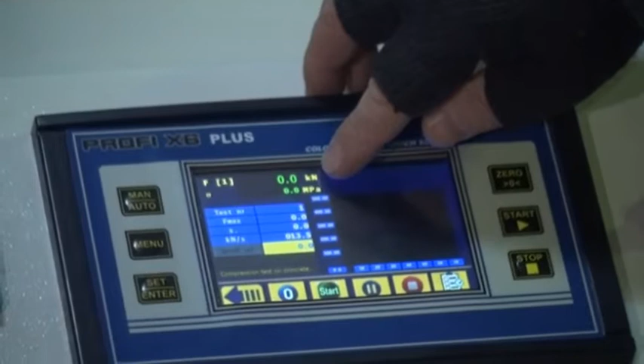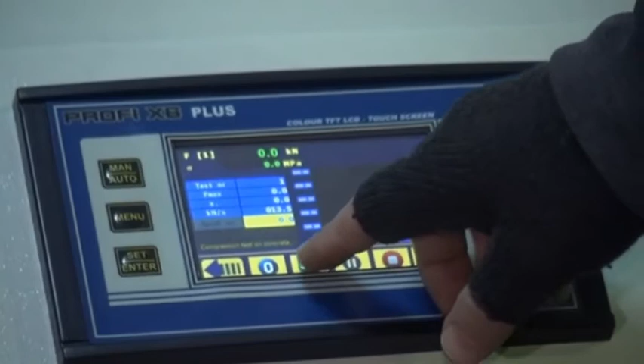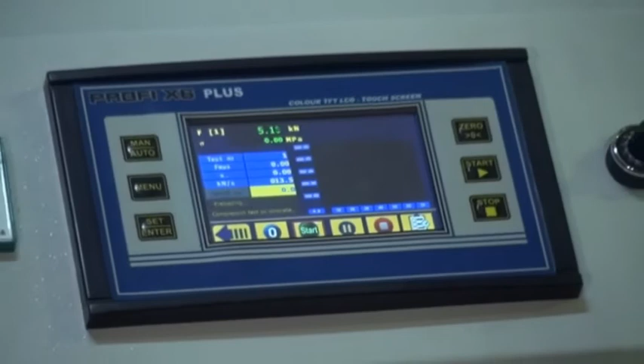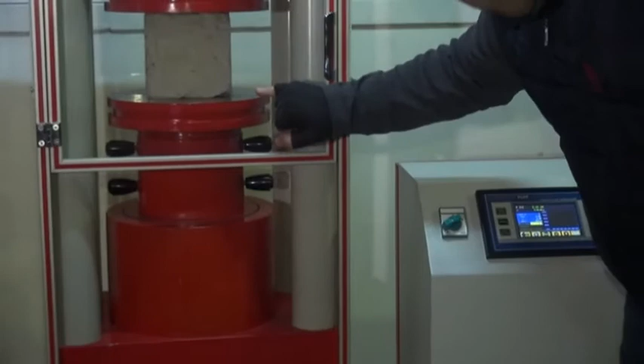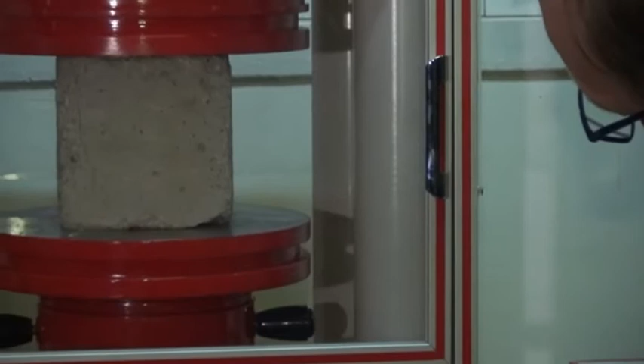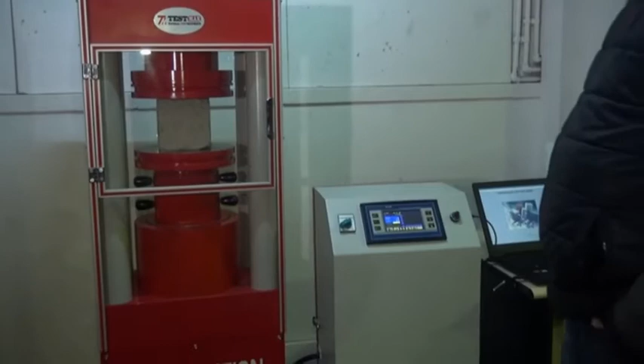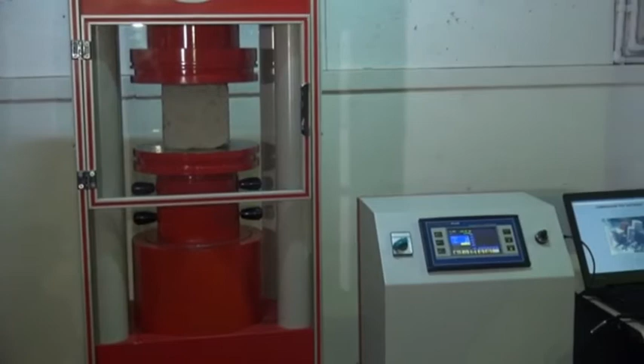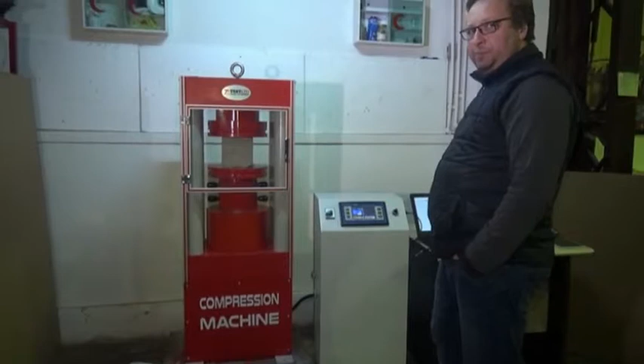Test screen shows the actual load on the machine in units of kilonewton, and stress in megapascal. Also test number, Fmax is the peak load, and test duration, test speed. If everything is ready, now we push the start button to start the test. Now test machine moves up with higher speed until it touches the sample on the upper plate, and then after it recognizes the touch point, it will change to test speed. Yes, now it has changed to test speed, and it automatically calculates the actual speed of loading and controls the speed by using the PID closed loop control.